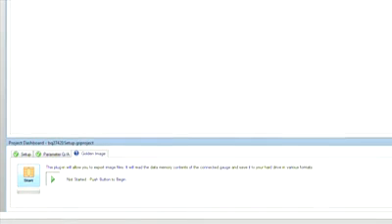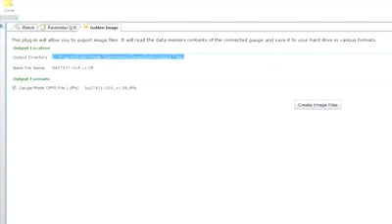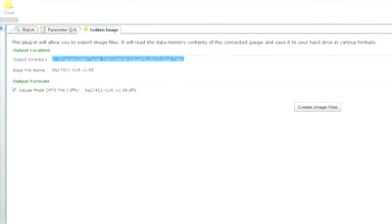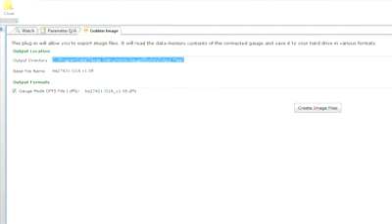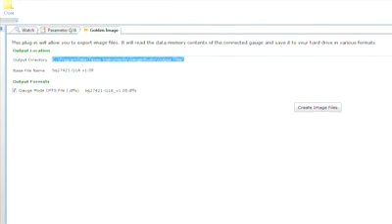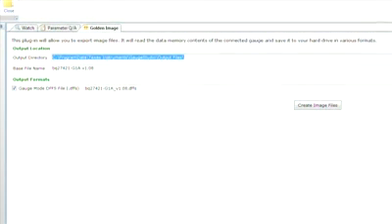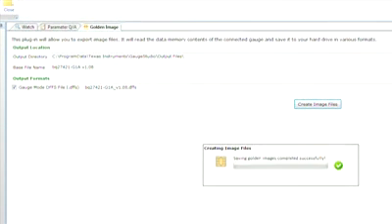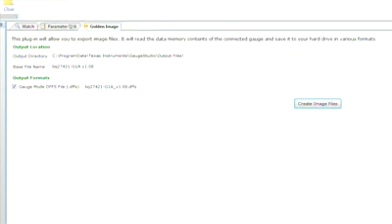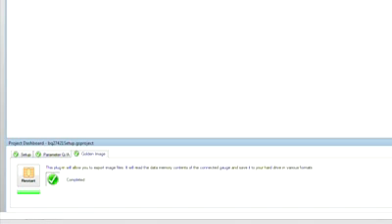Let's click on the Start button there, and you'll notice that up at the top you'll now have the Golden Image tab. That's just looking for an output directory and a file name for the golden image that we will provide. I will leave it at the basic defaults, just BQ27421 G1A, underscored with the firmware version. So let me click on Create Image Files, and this is now complete, and you can see in the project dashboard I have check marks on all my tabs. So at this point we've gone through the configuration process, and we've also exported a file that can be used in a production environment.